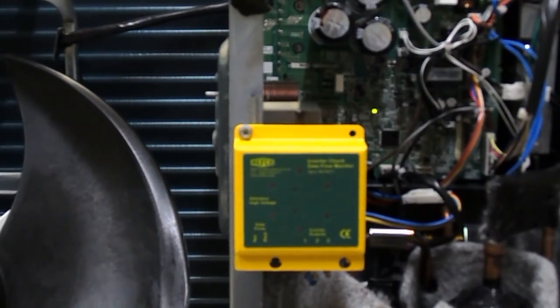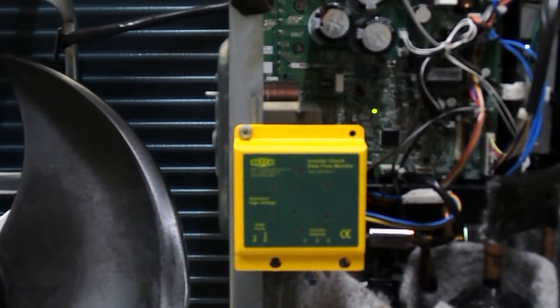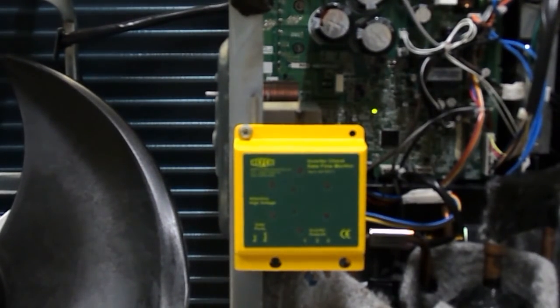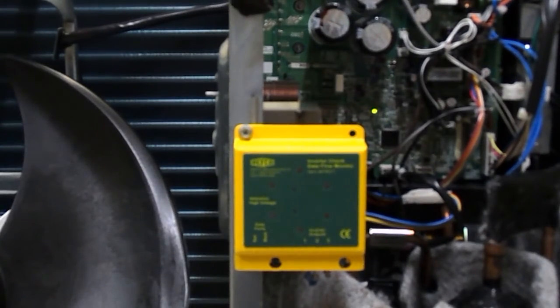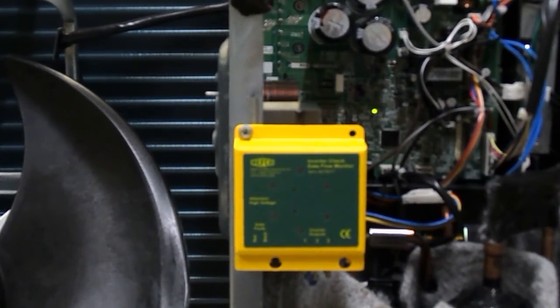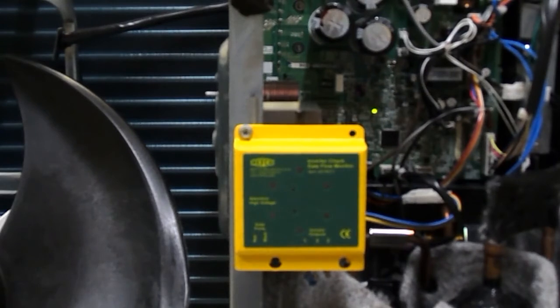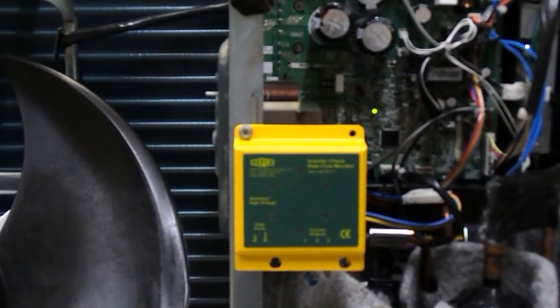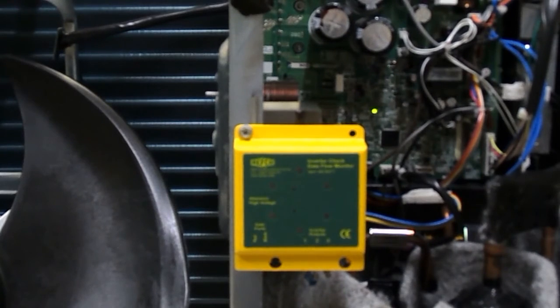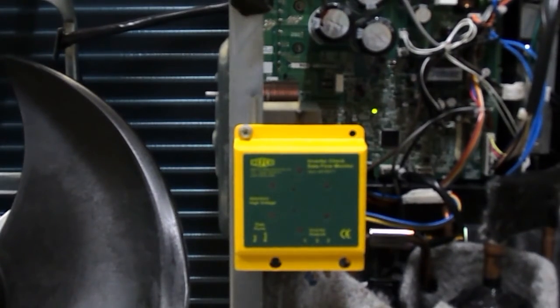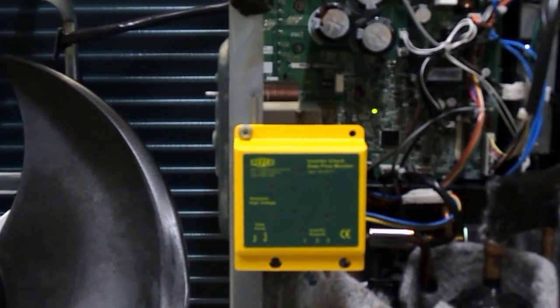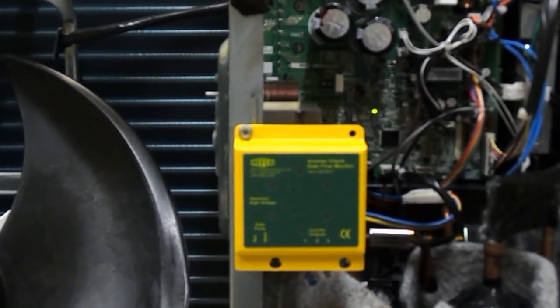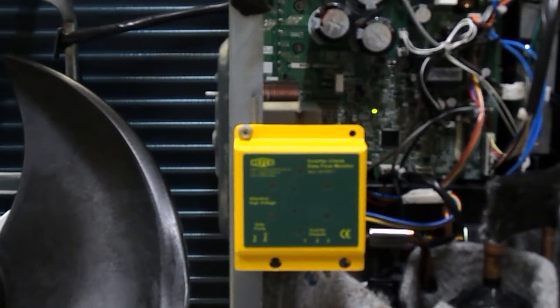Always make sure that you have proper risk assessments done on site and good job safety analysis there so that you can limit any chance of risk to yourself or others and approach it in a safe manner. This sort of test is also difficult because the wiring is put into the inverter module and it comes out to the compressor and it needs to be put somewhere safe. The advantage here is that we've got the box which is mounted to the unit and the holes in the testing tool allow it to be mounted safely.